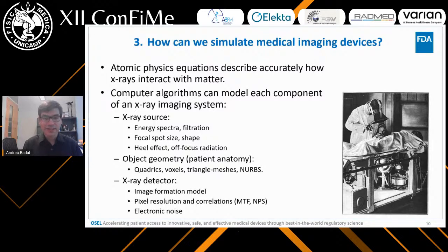That part of the physics is well known. Then the other part is using computational models to simulate the different parts of the X-ray imaging chain. You have an X-ray source that has its focal spot, and this needs to be modeled. You have a patient model that you have to model too. And then you have an X-ray detector that transforms these X-rays into a pixel value. There are some correlations in this detector that need to be modeled too, and there is some electronic noise. All this requires complex modeling, but essentially it's just these three models, because X-ray systems really haven't changed so much.